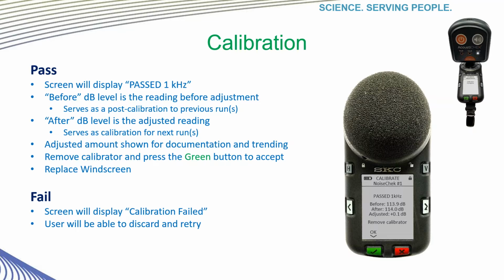From the pass screen, you would simply remove the calibrator and turn it off. Select the green OK key to exit the calibration. Now, if the calibration were to fail, repeat the calibration. If you have repeated failures, usually that's an indication that there's a potential problem with your microphone and that service may be required. Replace the windscreen with the black arrow on the collar pointed to the unlock padlock symbol, and then turn the windscreen clockwise until it clicks into place and is now pointed to the locked padlock symbol on the device.